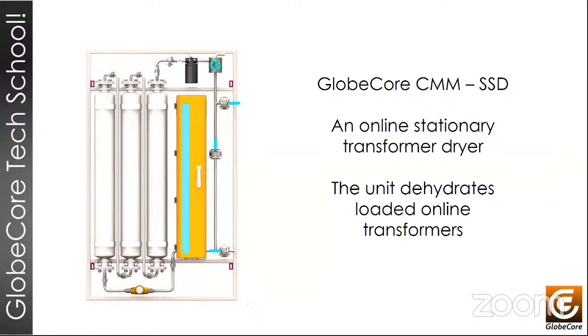This is an example of molecular filtration equipment. It's an inline dryer for the oil. It's connected to the transformer, and it operates continuously. And the flow rate of oil, the rate of circulation of oil in this equipment, is quite low, but it's compensated by the fact that it dries the oil continuously in cycles. So when it dehydrates the oil, a lot of moisture from the paper will go into the oil to restore the equilibrium, and therefore, in the process of using this thing, the moisture content in insulation paper will also decrease over time. Next slide, please.